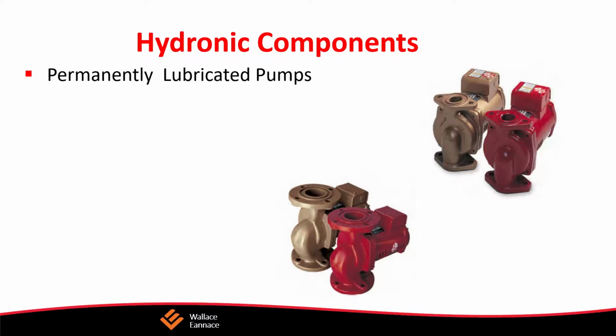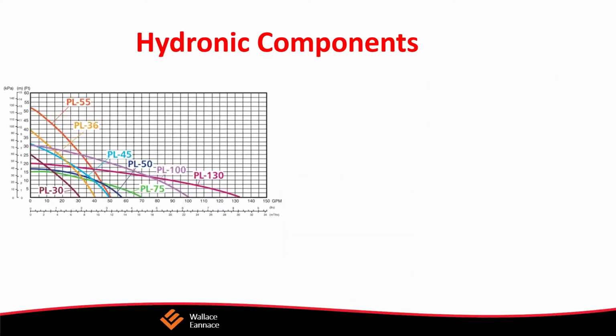Now, the length, we have 50 feet of baseboard, 50 feet of piping. That's 100 feet total. And we wanted to increase it by 50%. That gives me 150 feet. And again, we multiply it by 4 feet per 100. That's what we want for the pressure to make sure we eliminate velocity noise. So 150 times 0.04 is 6 feet of head. So for this particular baseboard loop, we need 2.4 GPM. We need to deliver 2.4 GPM at 6 feet of head.